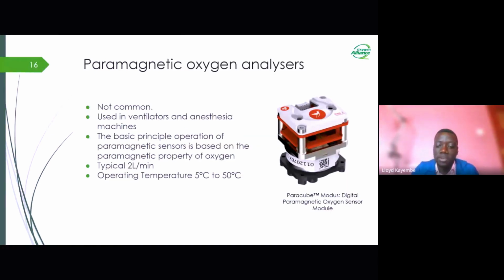So we can define paramagnetism as a form of magnetism where certain materials are weakly attracted by a strong field. Specifically, oxygen has these paramagnetic properties. These sensors typically measure oxygen with a maximum flow of 2 liters per minute, and they can operate between 5 to 50 degrees. To the right is an example of a paramagnetic oxygen sensor module. This one is a Paracube Modus digital paramagnetic oxygen sensor module. Next slide, please.